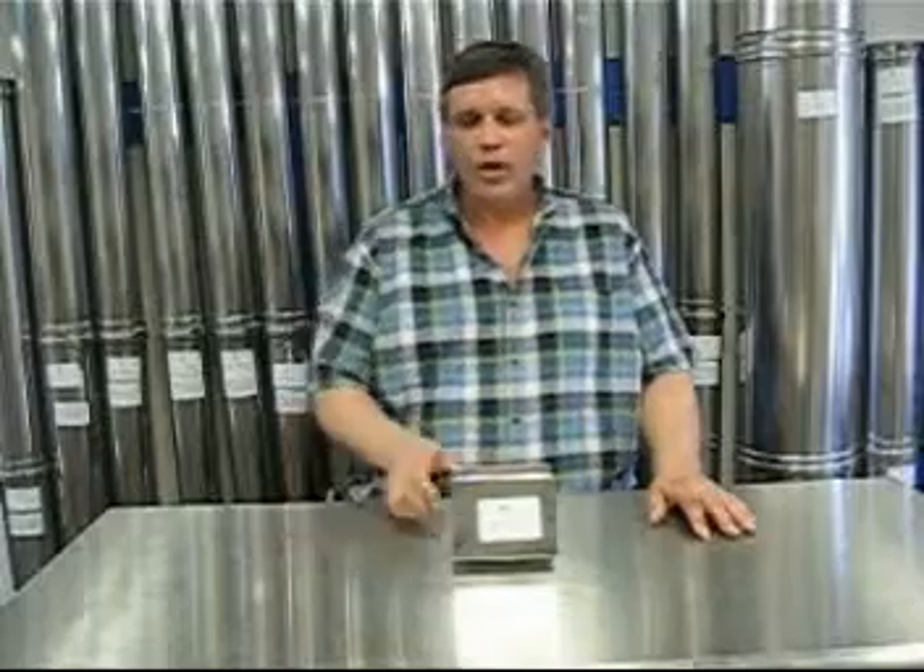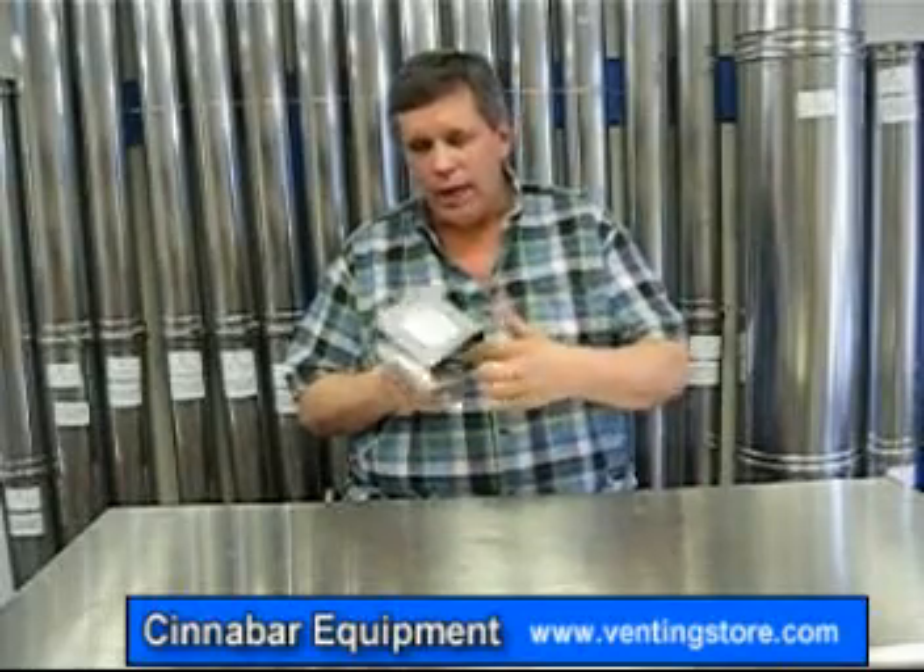Another termination option is the Z-Vent termination box. It has a 4 inch extension off the back, a built-in bird screen, and blows the exhaust out side to side. Now if you have vinyl siding on your house, you don't want to use this box because that hot flue gas will end up melting that vinyl siding. Also, with stucco or any type of brick, eventually it's going to end up discoloring that material.